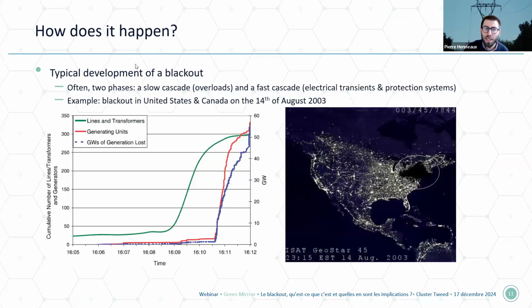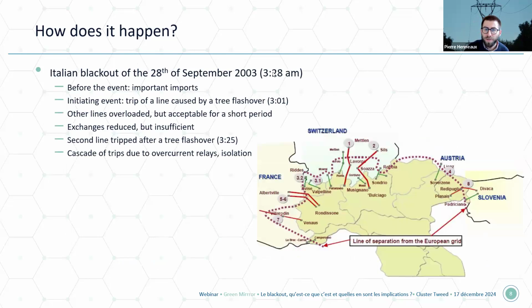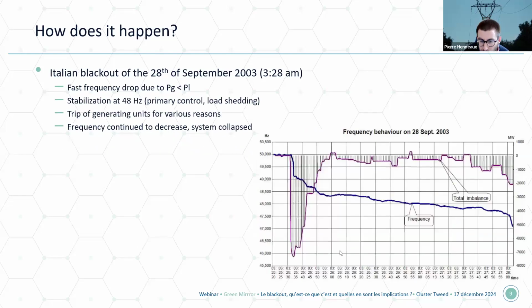Another thing that we see in Italy is that the first phase was quite slow. You see that you have a first event happening at 3:01, and then you need to wait 24 minutes to have the second event. But then after the second event, it starts to become quite fast. Everything will happen in a few minutes.